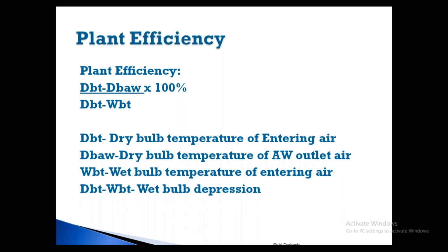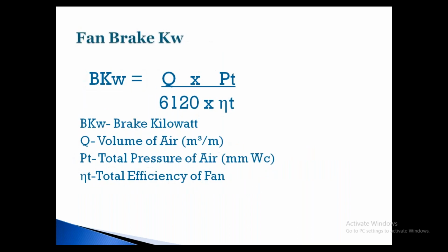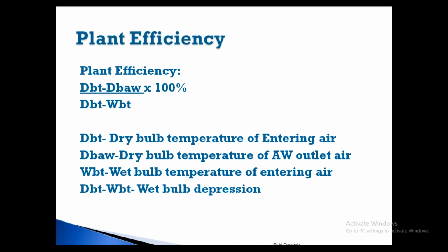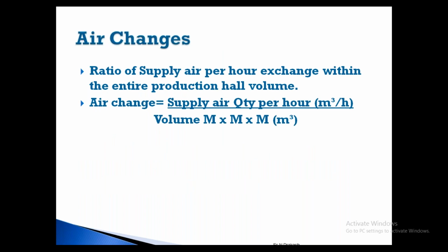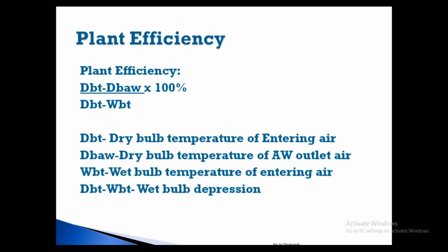If the water pressure is not there, the water will be delivering the required quantity, but it is not at proper pressure. It is low pressure, so it will not mix with the air. You will be consuming power in the pump motor, whereas you will not get the benefit by way of better efficiency. This problem will arise. That is why the plant efficiency, the air balancing and the total air changes, these three, if you are able to visualize and find out the reason for inefficiency and the reason for unbalance, then you can easily solve your power problem and other issues.